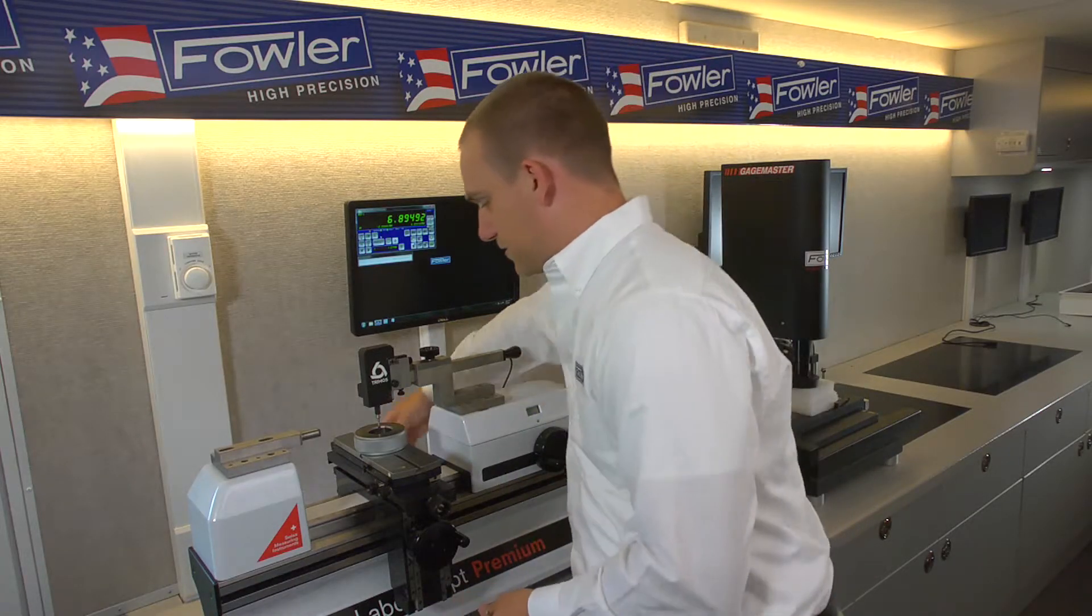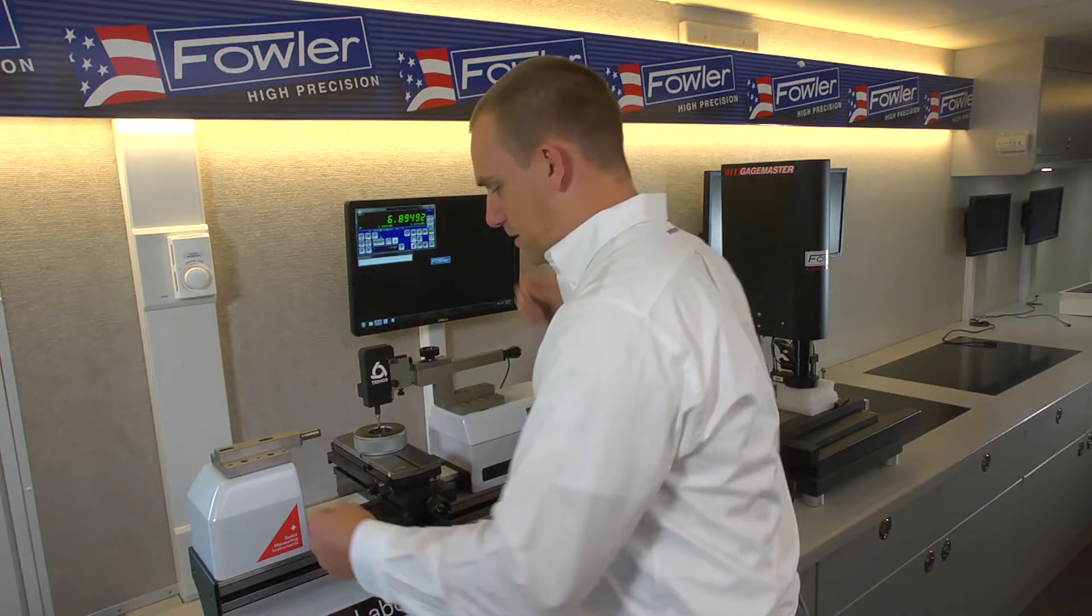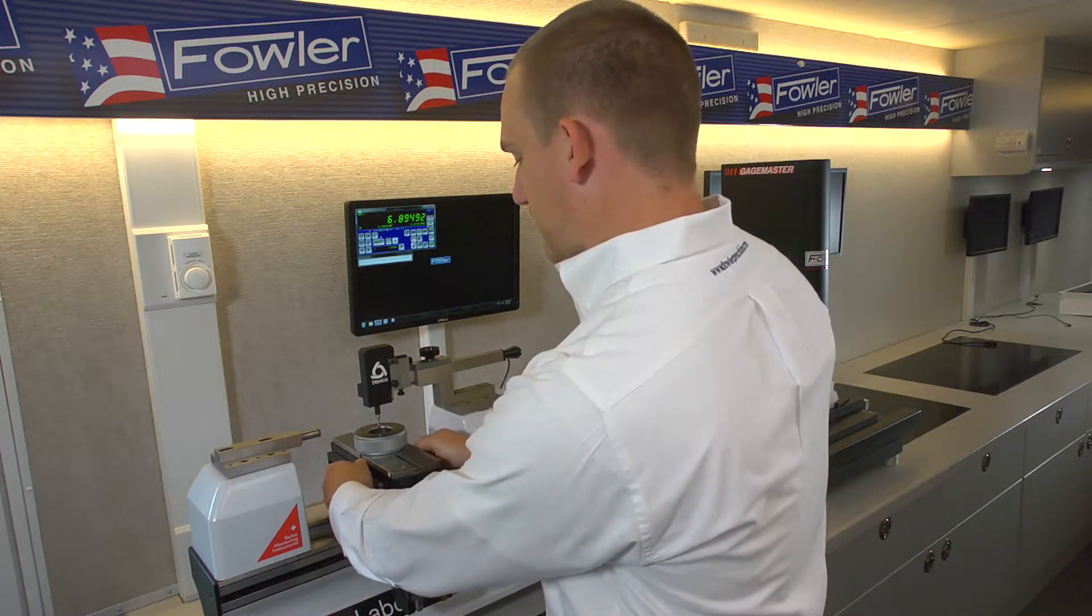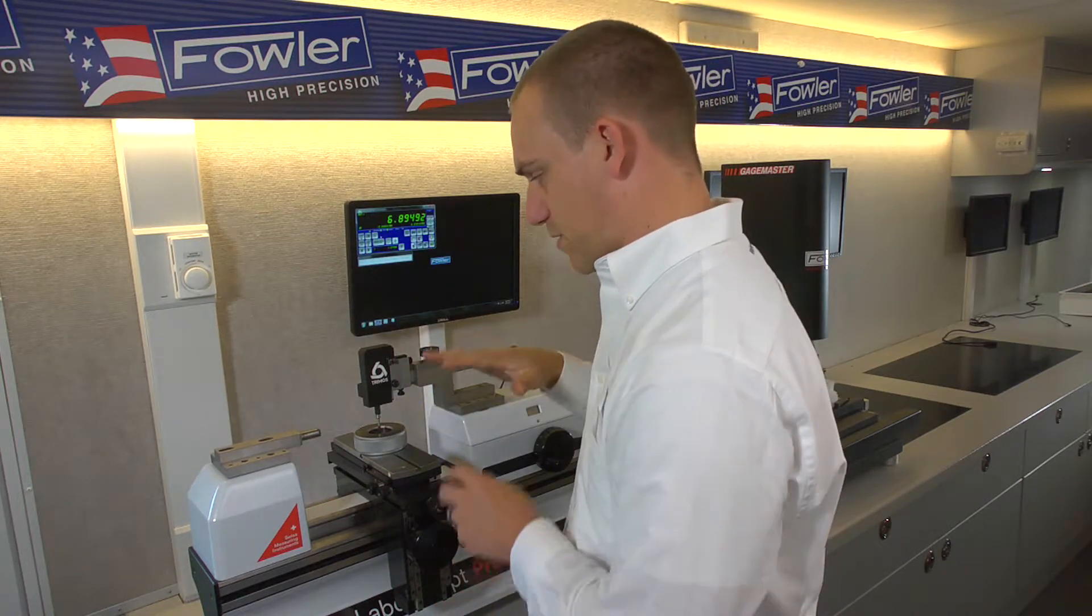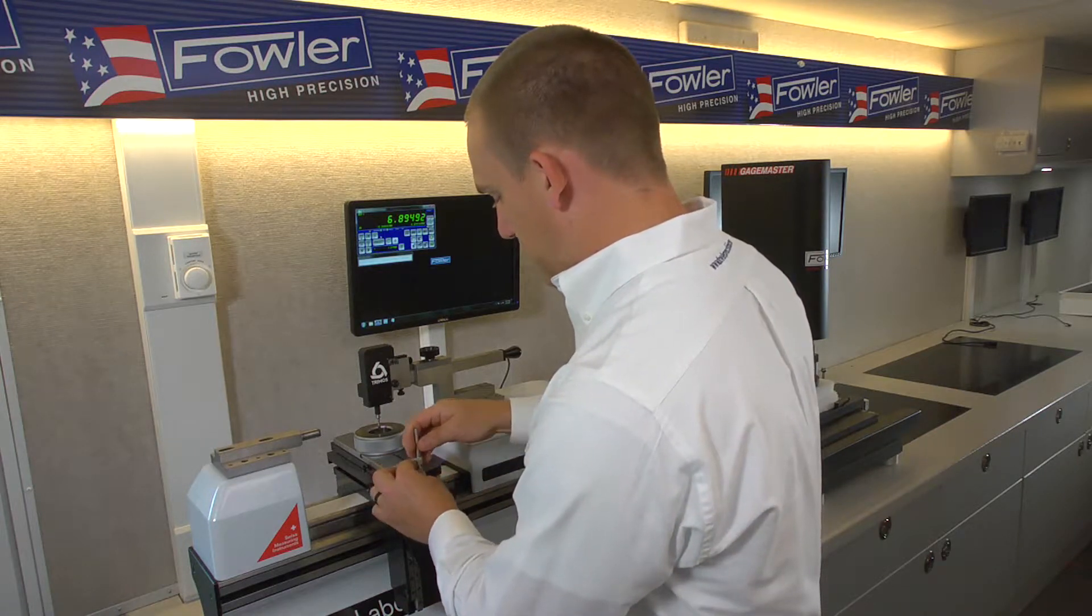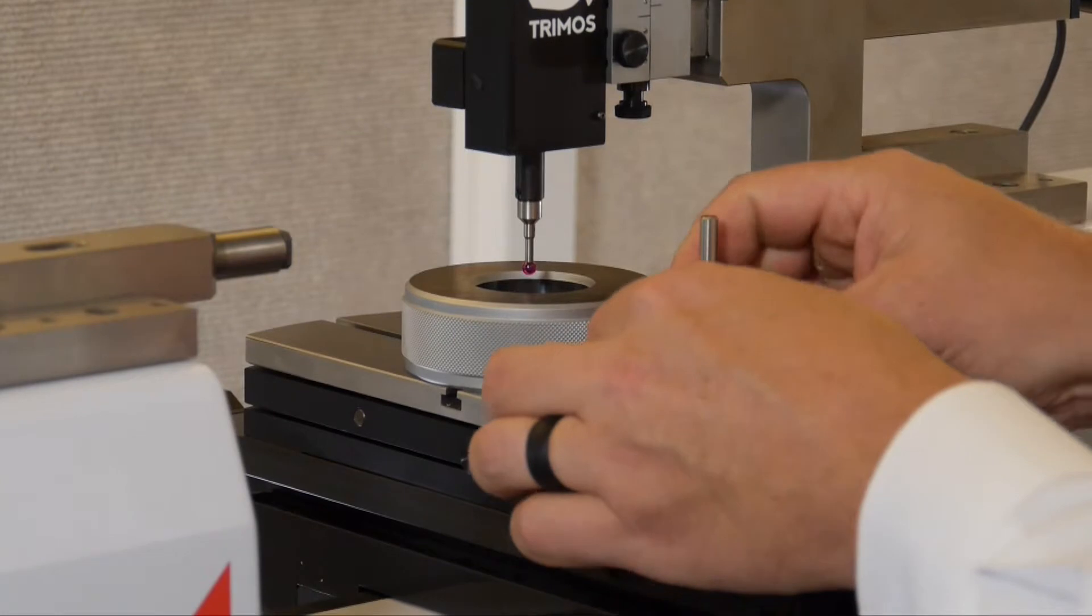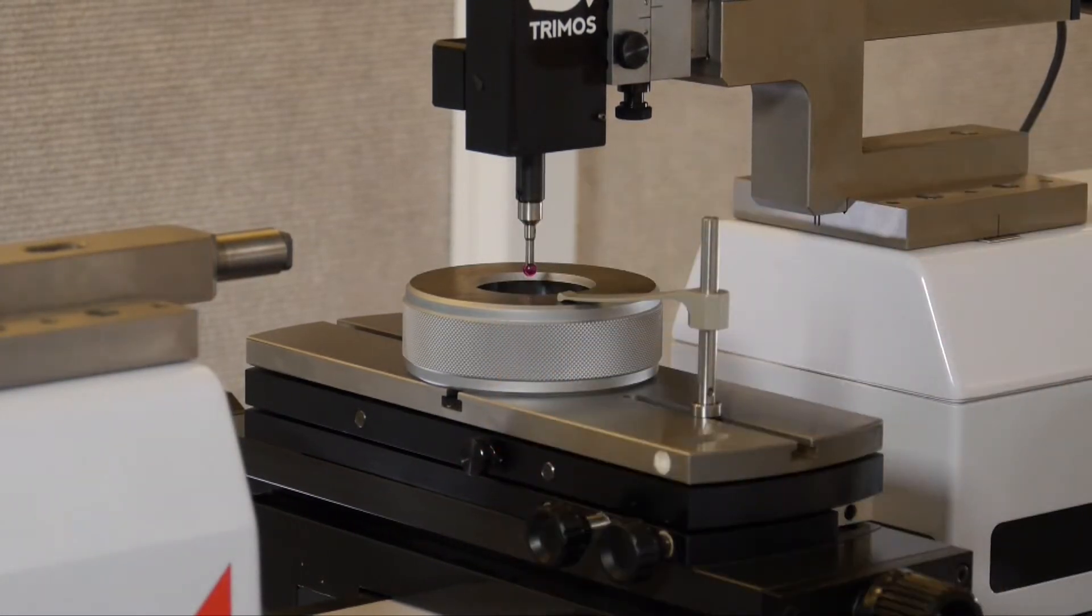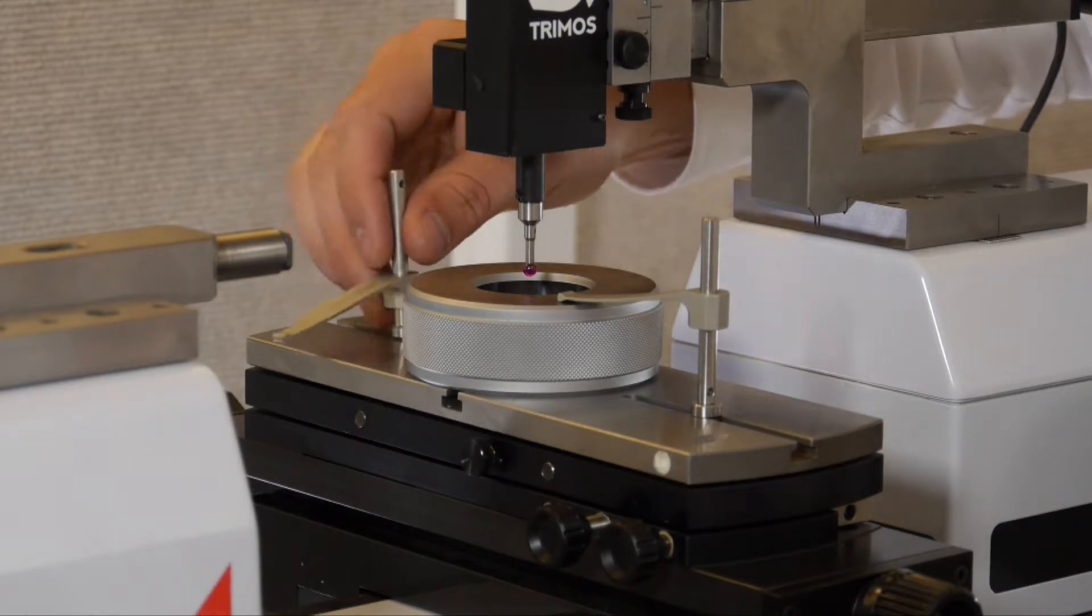First we want to make sure that our table is locked in place using these two knobs on the back. We want to make sure these side set screws are locked down because we don't want the table to move. We want our left measurement and our right measurement to be very solid. And we will lock the ring down to the table using some quick clamps, one in the front and another in the back.